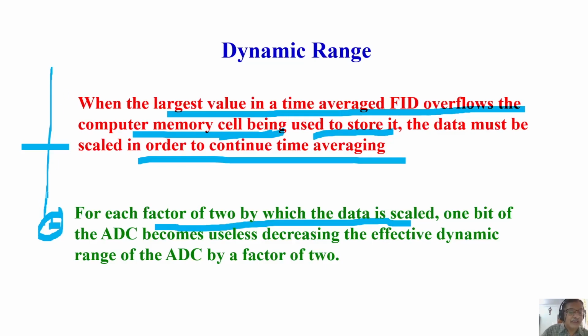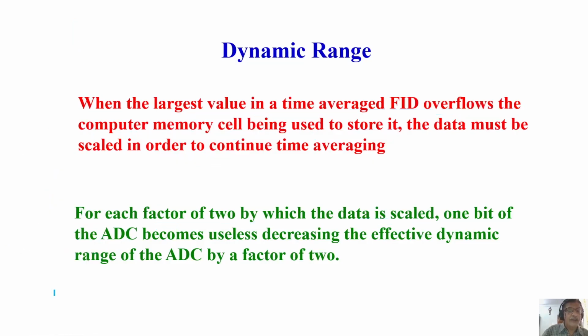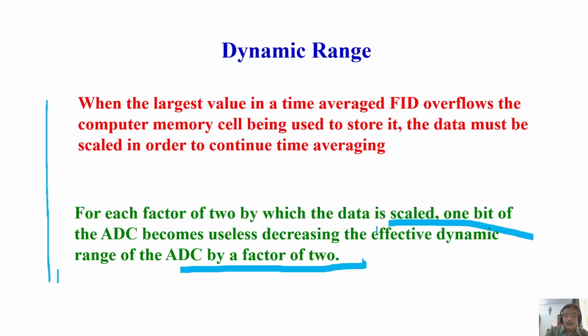Again keep acquiring. This fills faster. Now again it divides. This further goes down intensity. Signal intensity, because stronger signal fills the memory faster and keeps going up and up and up in intensity. Smaller peaks will not add up. In fact, after some time, the intensity will come down. It will not increase at all. Because every time memory is full, ADC is scaled by a factor of 2 to allow further accumulation of the data. This type of problem is called dynamic range problem.